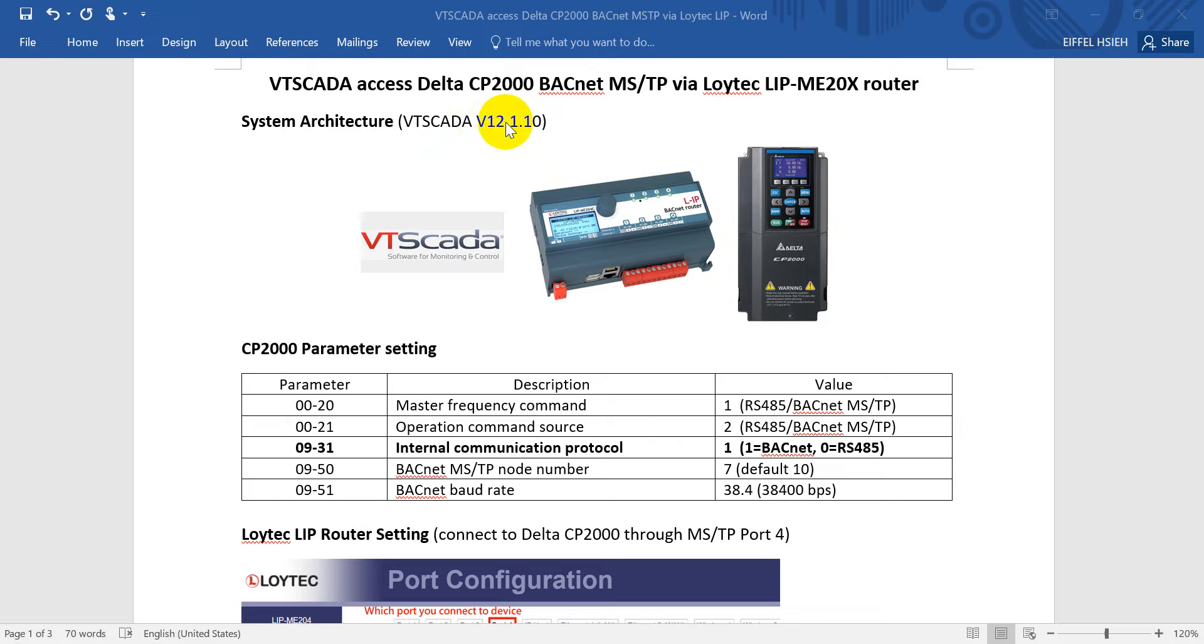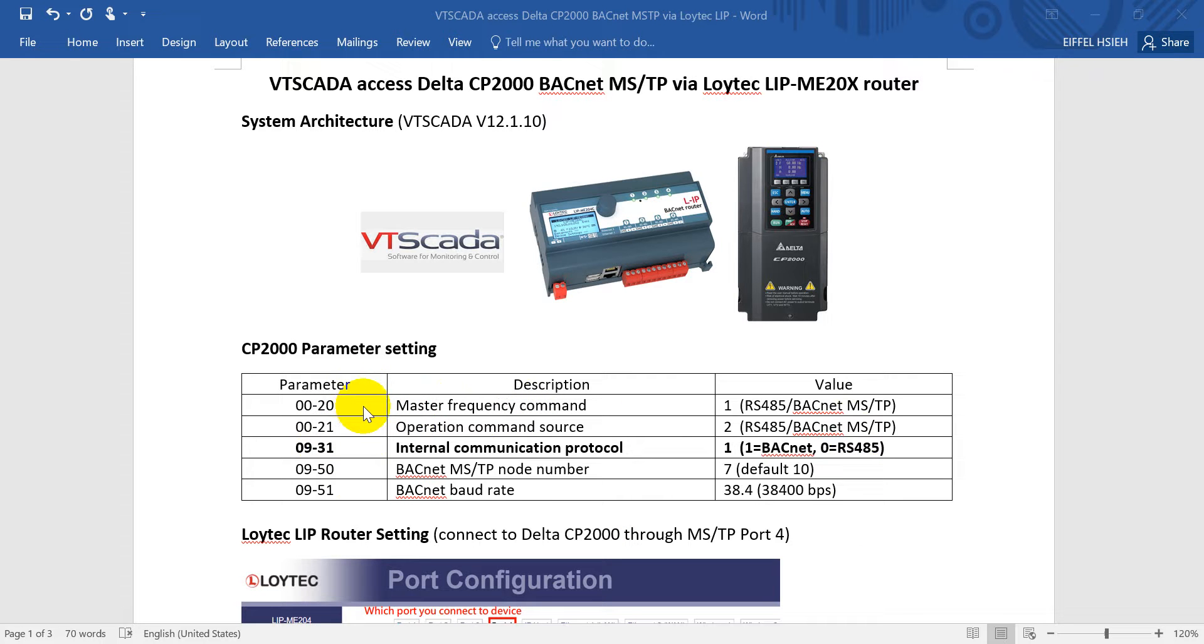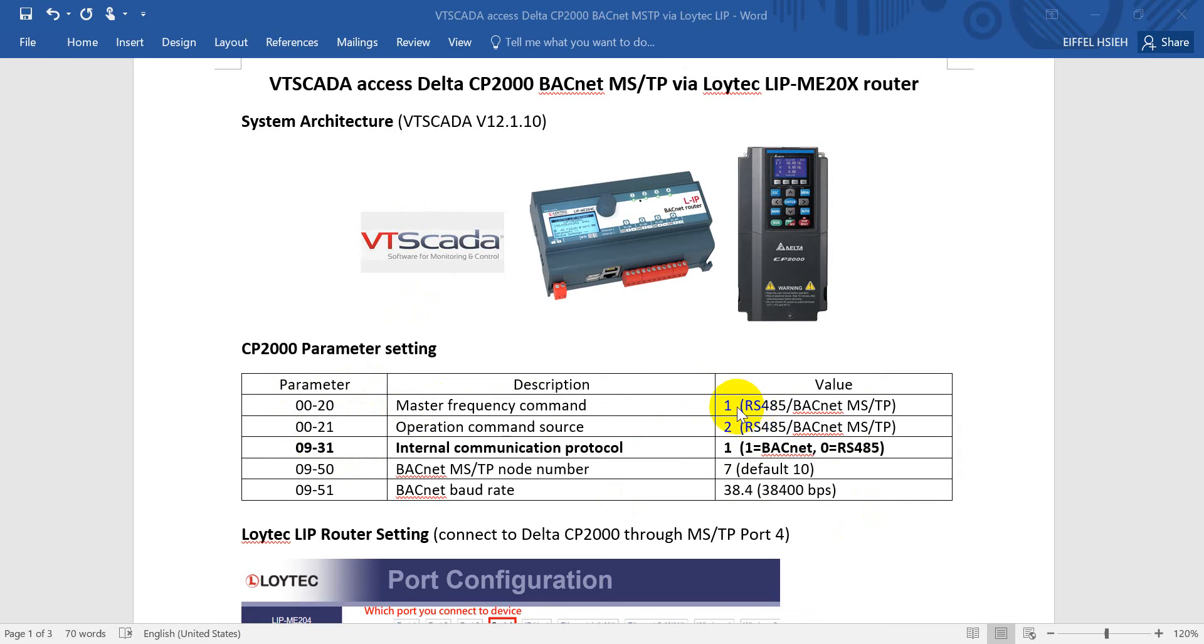Following are the CP2000 parameter settings. The most important parameters are these. If you want to modify the frequency command from VT SCADA, please remember to change parameters 00-20 and 00-21. Make this change to RS485 or BACnet MSTP.